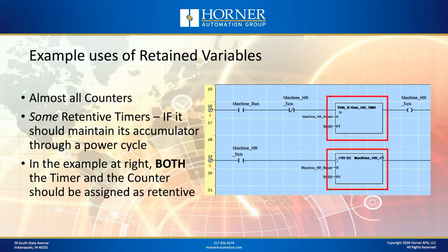All right, now let's talk about counters. In most cases, you're going to want counters to be retained. Now, there are going to be exceptions, of course, but a lot of the time, you want the counter to start up after the power cycle with the value it had before the power cycle.